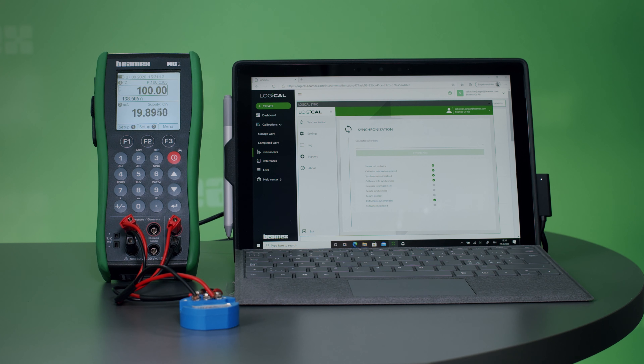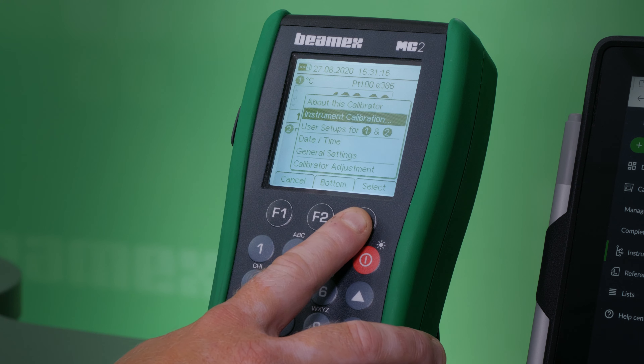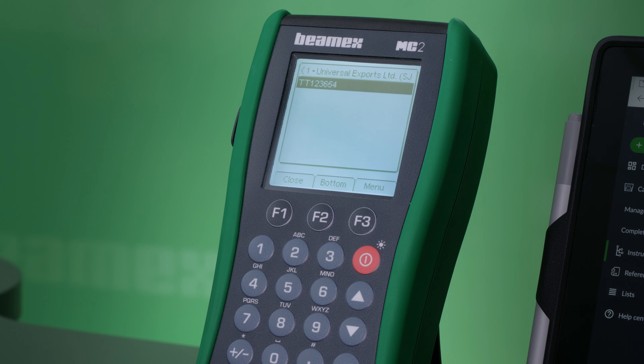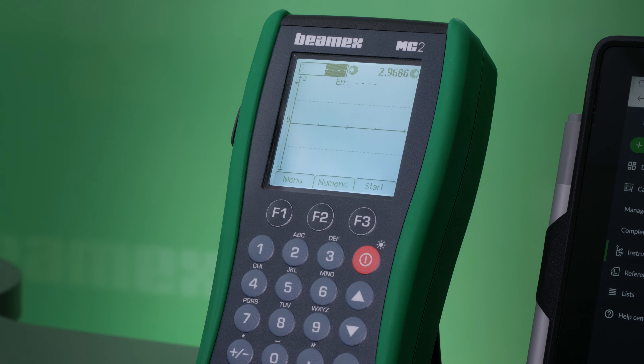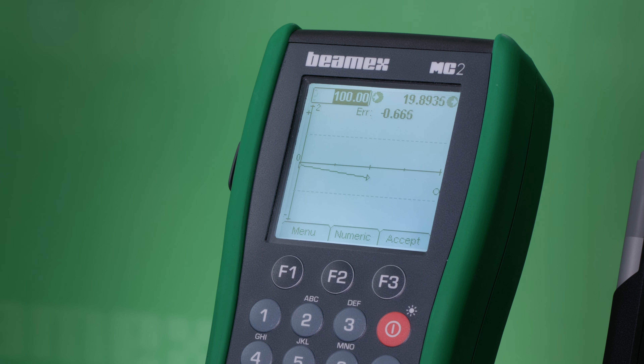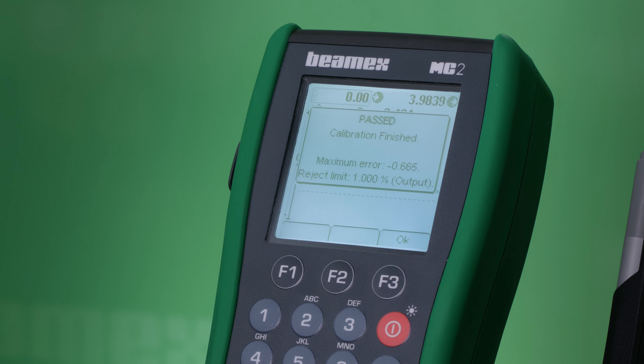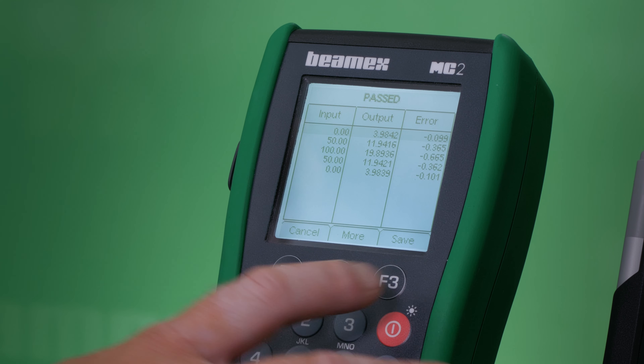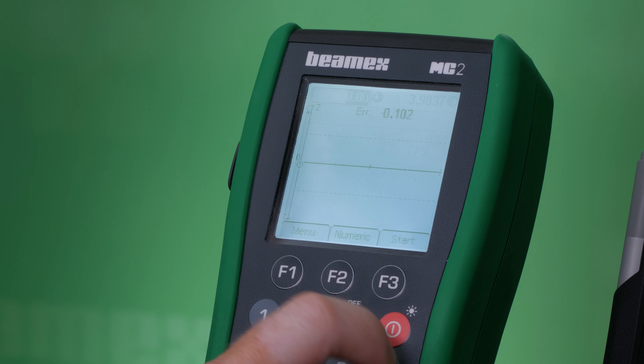To execute the calibration event itself, go to the MC2 menu, choose instrument calibration, and you will be presented with the instrument that you just synchronized from LOGiCAL. In this view you will be shown both the upper and lower error limits together with the zero line. When I hit start, the calibrator will then perform the calibration for you. It will show you where the input and output signals are and record the data to the memory. You will then be presented with the passed or failed result — in this case it was passed. I can also view the results in both graphical and numerical views. You can choose saved results as found and it's stored.